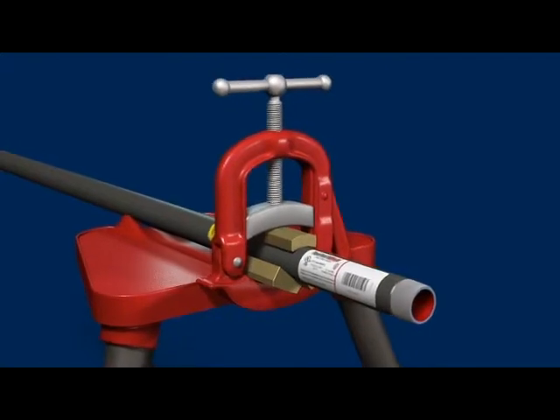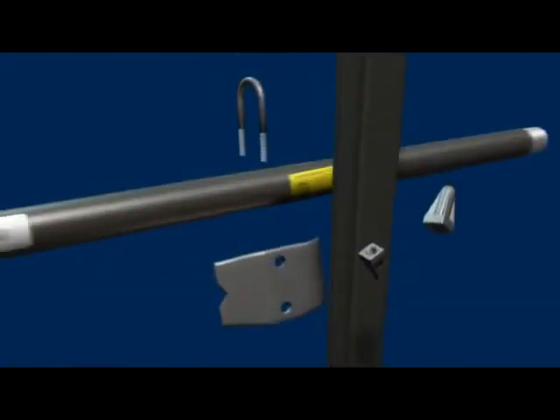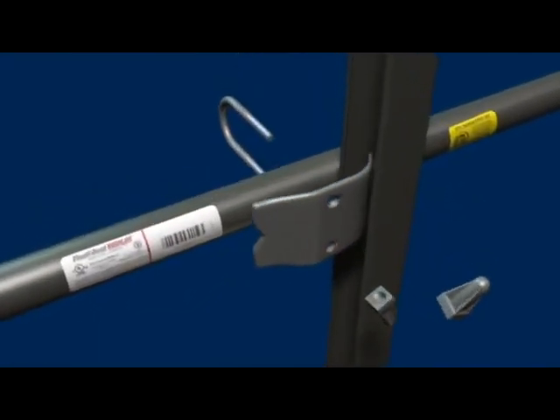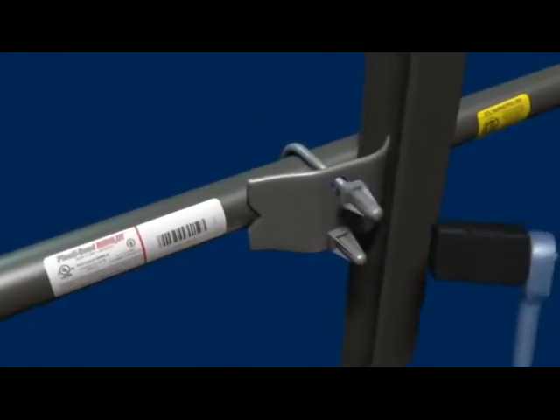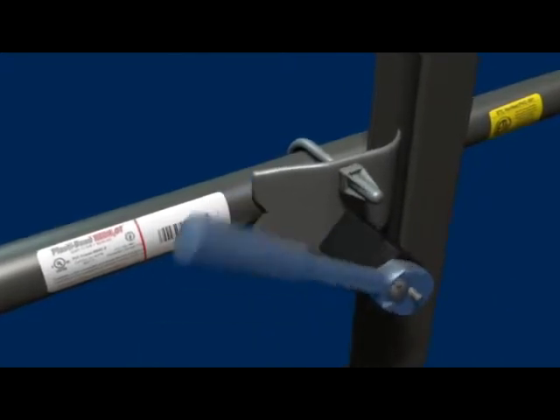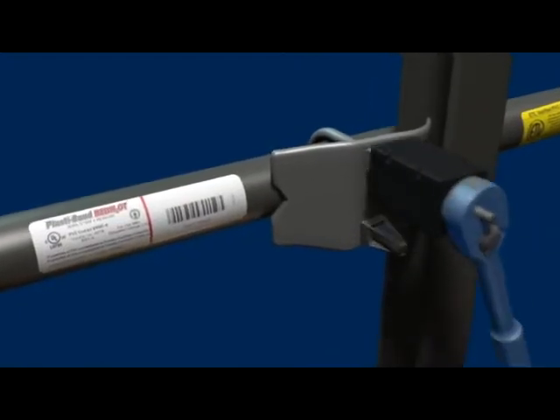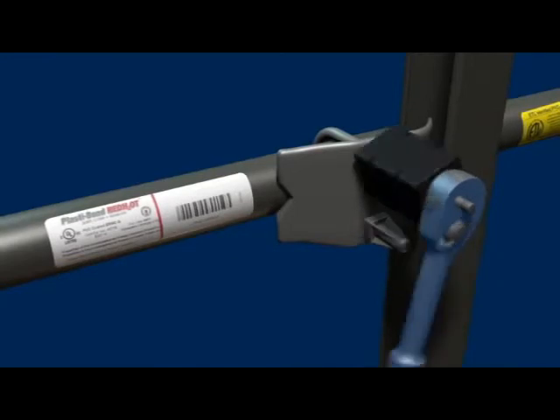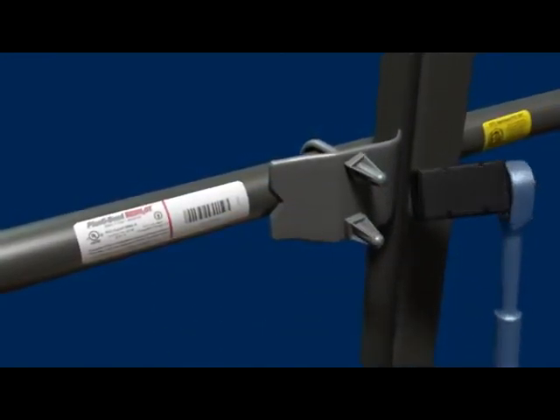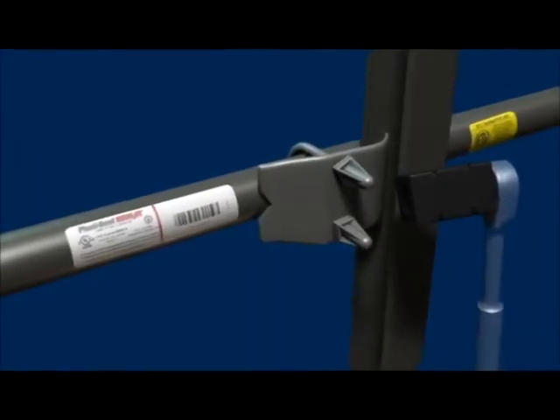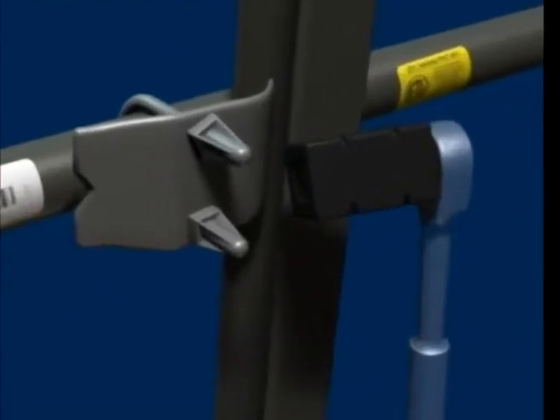When ordering Jaws 3, be sure to specify the vise model you are using. Use the PlastiBond plastic socket and standard three-eighth inch ratchet to speed up U-bolt and beam clamp installation. The plastic socket prevents abrasion and cracking of encapsulated nuts, which may be caused by pliers or wrenches, and assures a tight seal between the nut and the saddle. The three-eighths inch PlastiSocket fits nuts for one-half inch through two-inch clamps. The five-eighths inch PlastiSocket fits nuts for two and one-half inch and larger sizes. Both PlastiSockets fit a standard three-eighths inch drive ratchet wrench.